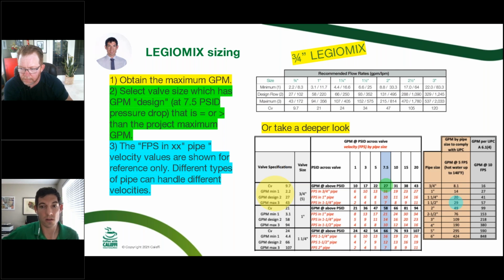So it's going to look a little weird on the wall, but at 1.5 inch piping, we're at 5 feet per second at 29 GPM, and then the Legio mix at the 3/4 inch is going to be the right valve in that application. So you could go to a 1 inch, and you would be close enough in this case, but it is something that is going to look a little strange, but is going to be sized properly as you walk through this chart to leave that 1.5 inch trunk that connects all the way down to the 3/4 inch Legio mix. You want to do that as close to the Legio mix as possible.